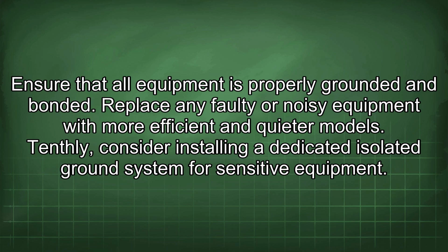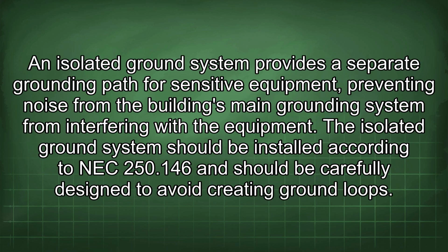Tenthly, consider installing a dedicated isolated ground system for sensitive equipment. An isolated ground system provides a separate grounding path for sensitive equipment, preventing noise from the building's main grounding system from interfering with the equipment. The isolated ground system should be installed according to NEC 250.146 and should be carefully designed to avoid creating ground loops.